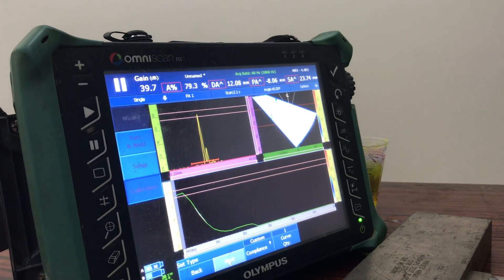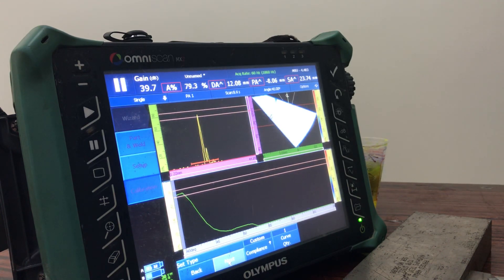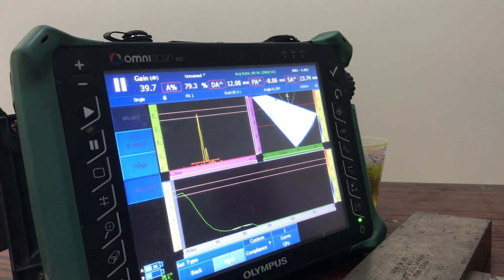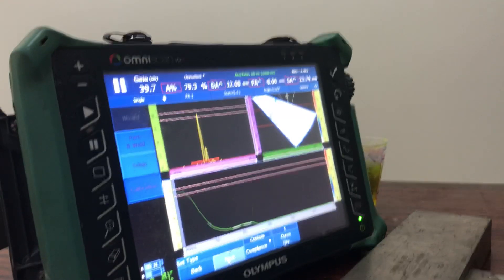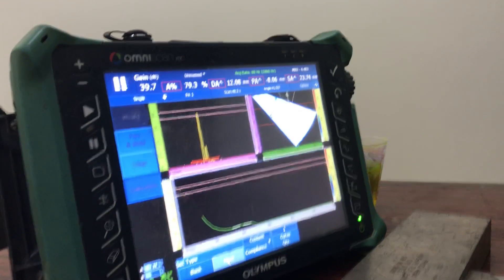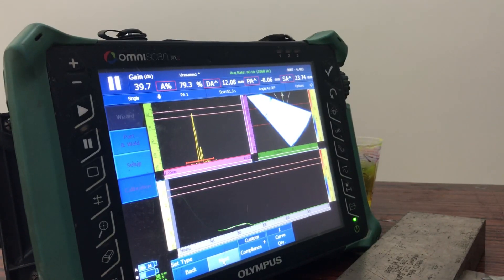Our thickness is 15 mm. For TCG calibration, we need a minimum of three points. The first point should be at approximately half the thickness. The second point should be nearby the full thickness — so around 16 or 17 mm. The third point should be at double the thickness or above, so around 30 mm or more.